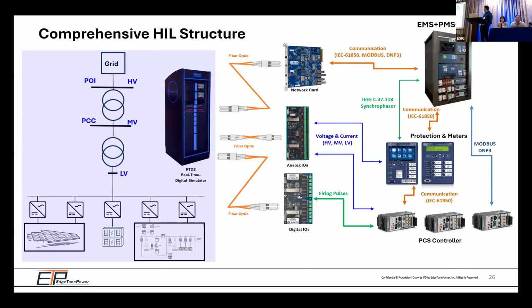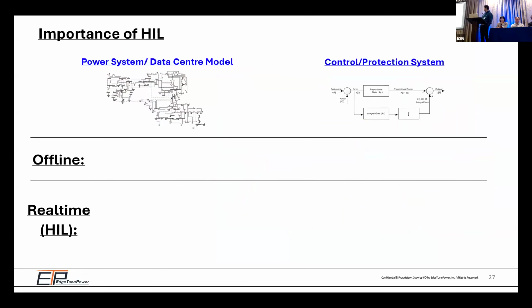And we also tested the meter. The reason is that these pictures are very, very familiar to all of you. These are Schweitzer devices, right? They have the IEEE C37 synchrophasor communication protocol, which is a very fast protocol. But if you want to represent that protocol, the simulator itself cannot do that. And you have to have this meter to represent the synchrophasor between the meter and the high-level management system of the data center. So you see we have multiple devices under test.